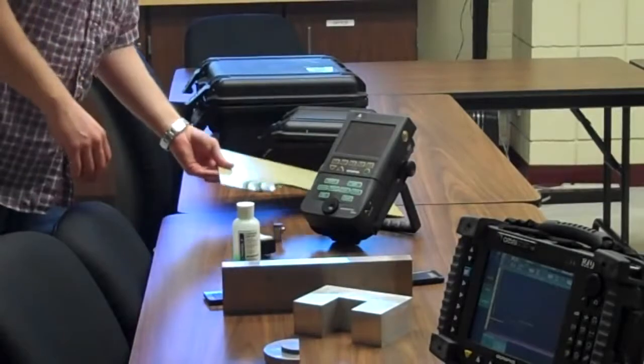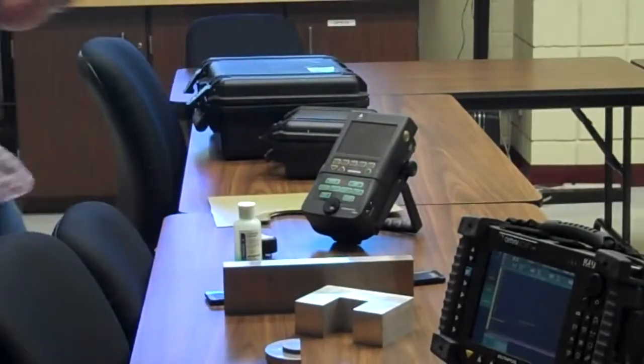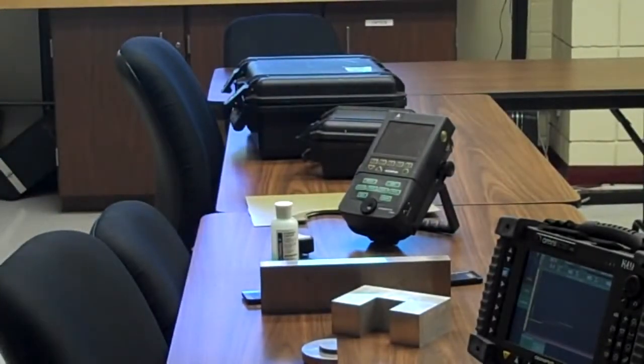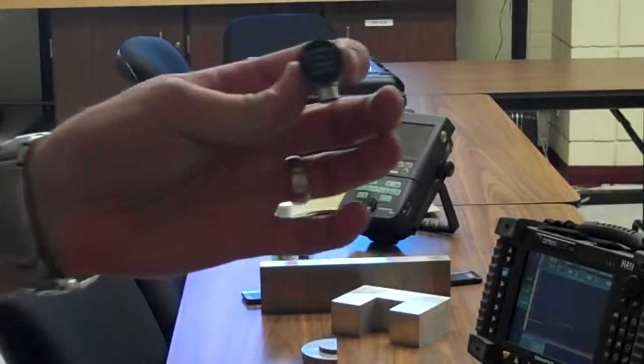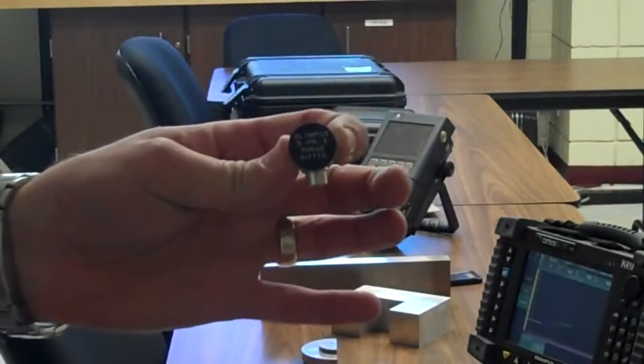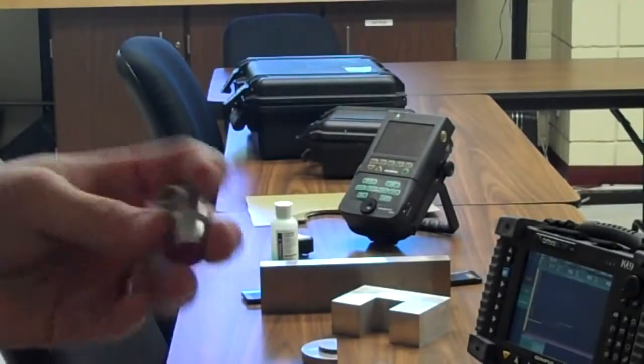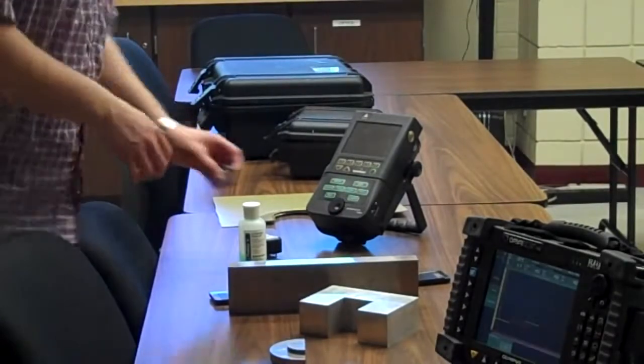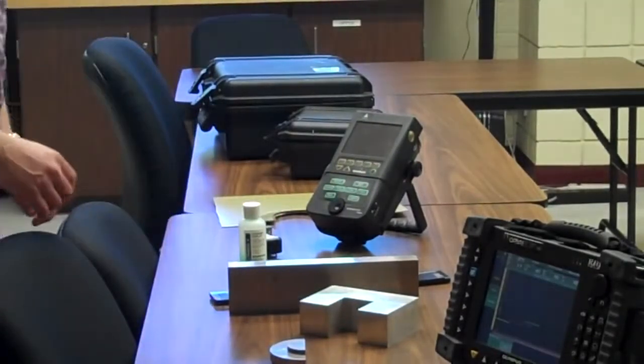We've got a Bondmaster 1000 E Plus here, got a little resonance probe to go with it. You guys have read a little bit about resonance. This one's 110 kilohertz, low frequency. This is actually in the sonic range. Well, it's still in the ultrasonic range, but it's outside of what we generally do ultrasound with. So not a huge problem there.